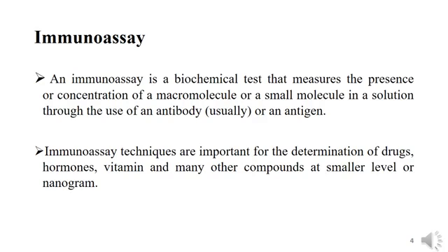The use of a calibrator is often employed in immunoassay. Calibrators are solutions that are known to contain the analyte in question, and the concentration of this analyte is generally known. Comparison of an assay response to a real sample against the assay response produced by the calibrator makes it possible to interpret the signal strength in terms of presence or concentration of analyte in the sample.